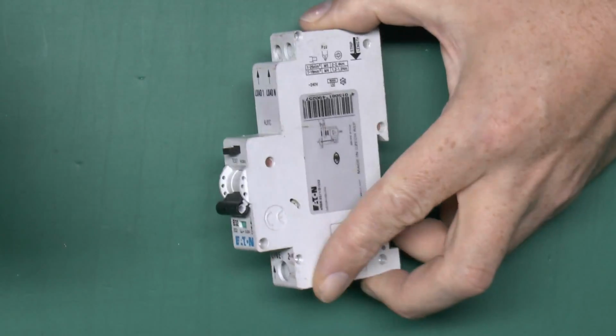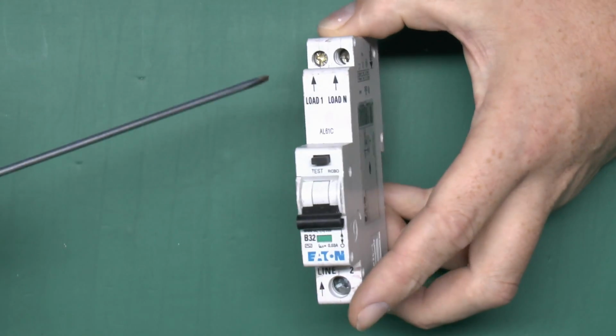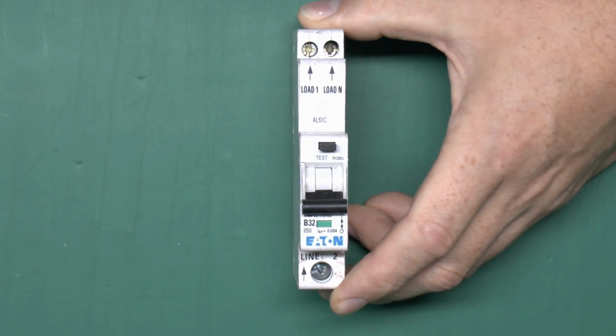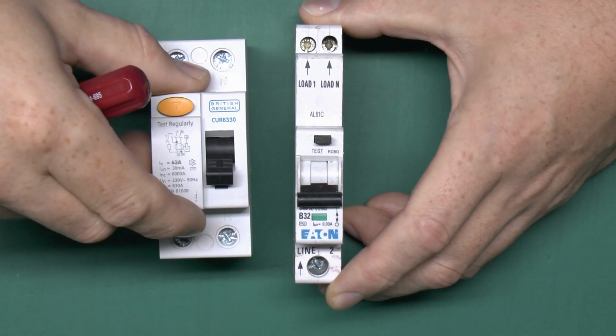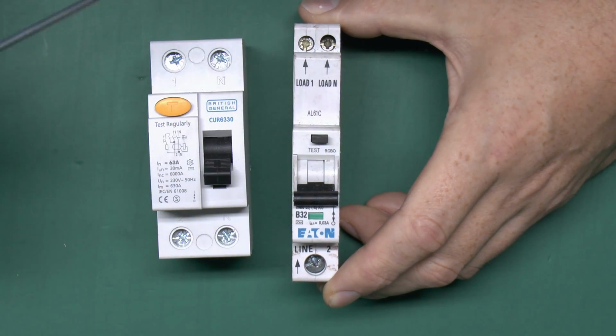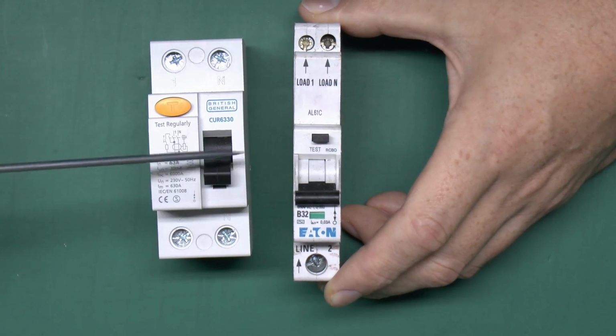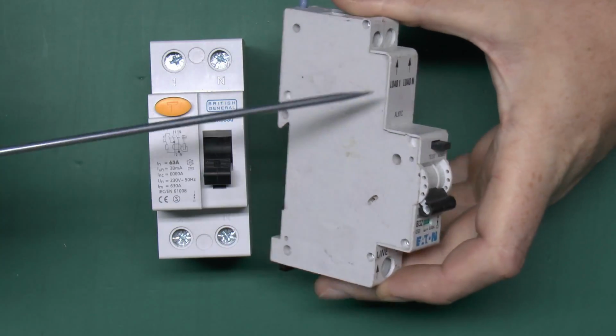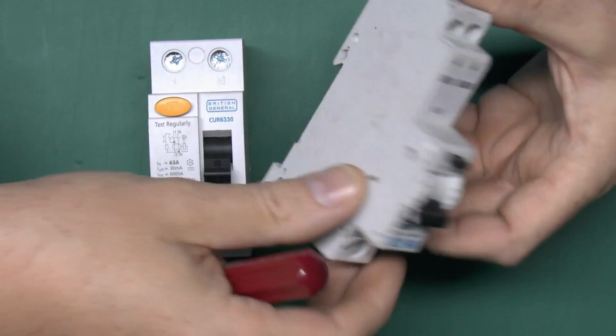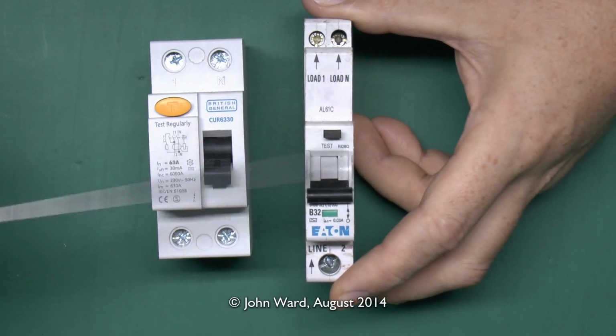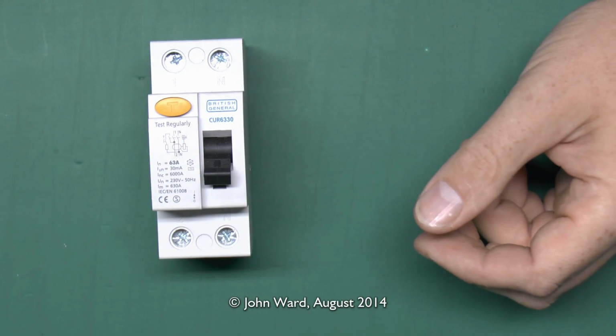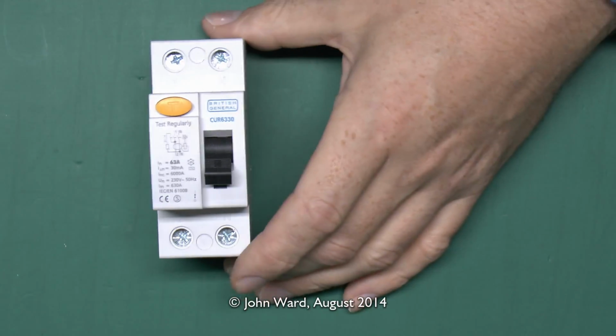However, unless you've specifically purchased one of these devices with this functionality built in, then of course your standard RCD is not going to do any of those things. It only applies in this particular case where it's essentially a circuit breaker and the RCD combined into a single unit. However, we're not going to be looking at those this time. That's just to point out that these things do exist. But again, we'll be looking at those in a separate video.